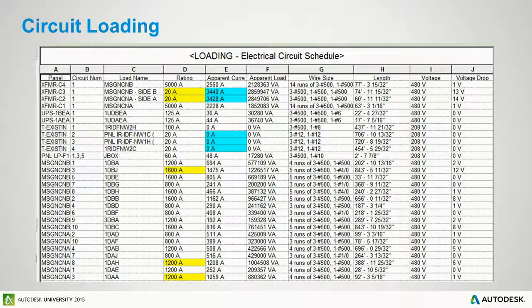So for items where we have one motor, and it's from the distribution panel to the motor, the length is decently correct. It's normally within 5-10 feet. And that gets into the coordination of when we design, we determine what route we think they're going to use, and then the contractor does his coordination drawings, and he may or may not use the route that we designed. So we're designing the voltage drop and the wire size to the best of our ability based off of the routes that we put in our design.